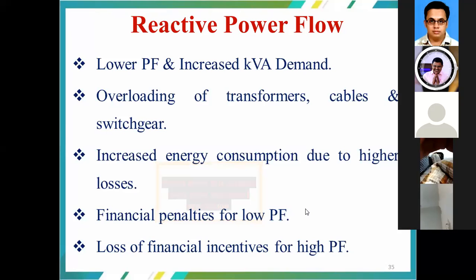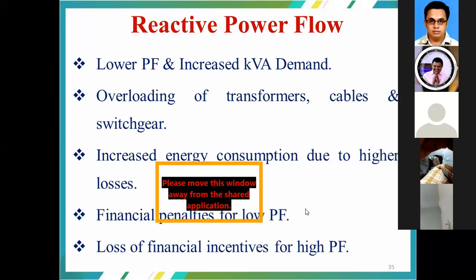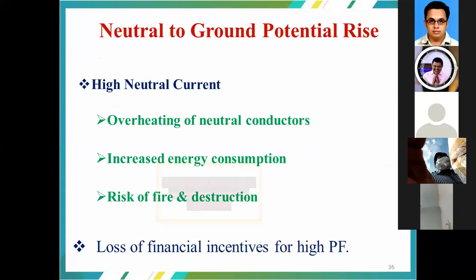The increased energy consumption is due to the higher losses because of the unwanted frequencies. The power losses are going to be higher, which increases the losses also. And if the power factor is lesser, you are going to have a penalty, as far as the Central Electricity Regulations are concerned, for a lower power factor, and this is going to have implications for the financial operation of the company or the organization. And because of the lower power factor we are going to lose the financial incentives, which are often given to higher power factor operation.